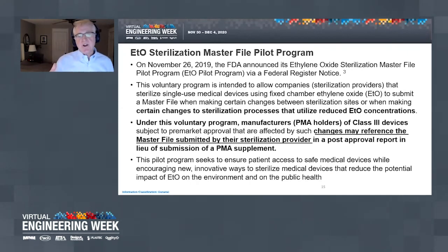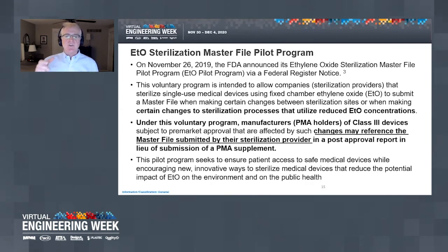What is central to the Master File Program is to allow for changes made to the sterilization process related to the reduction of the use of EO in your cycle. Given the variety of EO cycles currently being used, there's a number of changes that fall under this umbrella. The advantage of the Master File Program is twofold. Either one, a company, an OEM like Boston Scientific or BD, holds a master file, or two, a contract sterilizer provider holds a master file. There isn't one yet, at least that's on the website. If your company holds the master file, like Boston Scientific, you can annual report the changes to your process for your PMA products related to reducing EO, and that includes adding new sites, reducing EOs, adding chambers. There's a variety, even changing out a pump to accommodate the new reduced EO cycle, including any facility changes to move towards zero emissions.